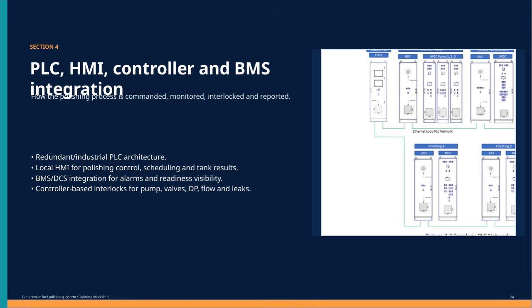Next, a local human-machine interface, or HMI, allows operators to control polishing, schedule operations, and review tank results directly on-site. The HMI provides a user-friendly way to monitor and adjust the process in real time. Furthermore, the polishing system integrates seamlessly with the BMS and Distributed Control System, or DCS. This integration offers alarms and readiness status visibility at a higher supervisory level, ensuring any issues are promptly detected and addressed.